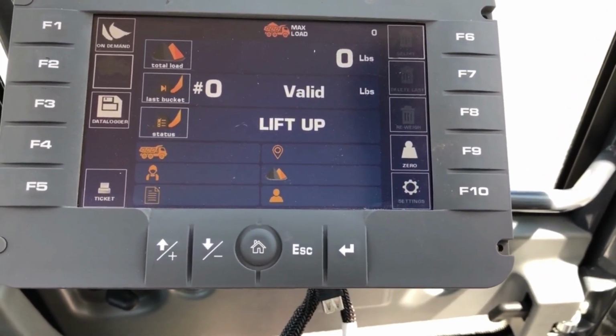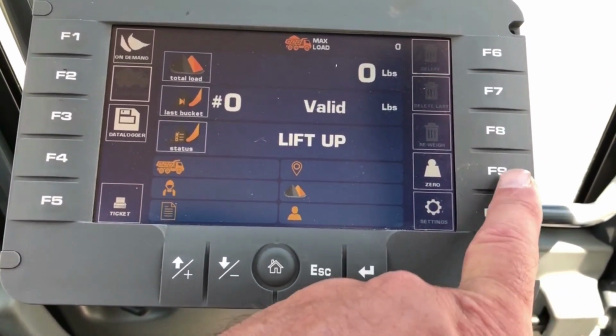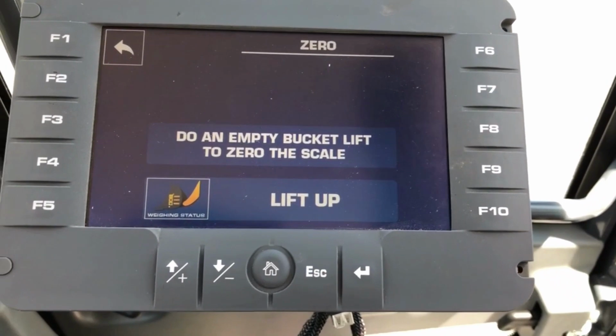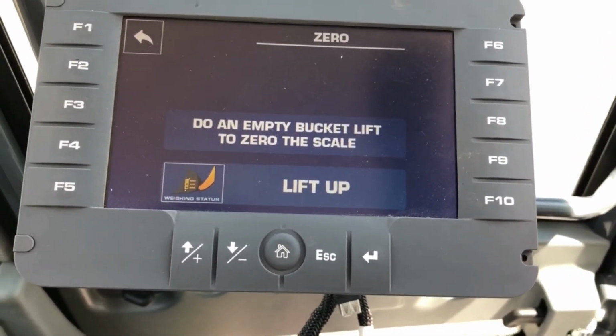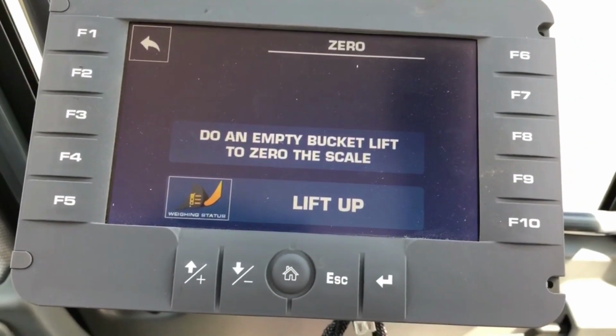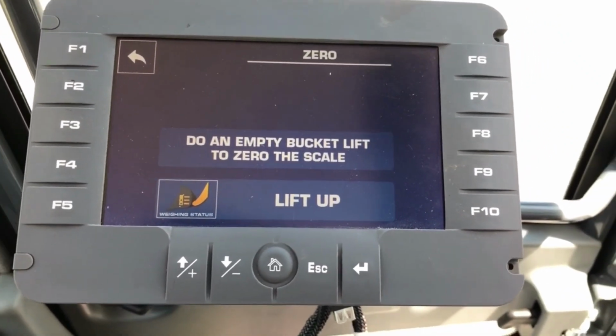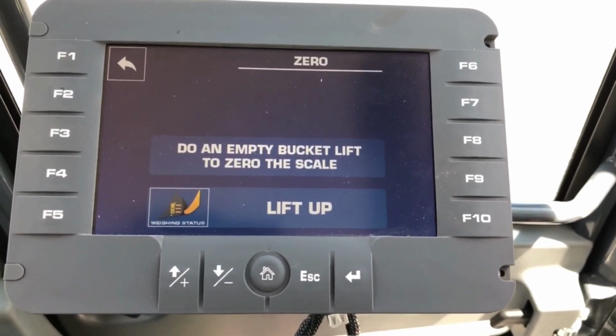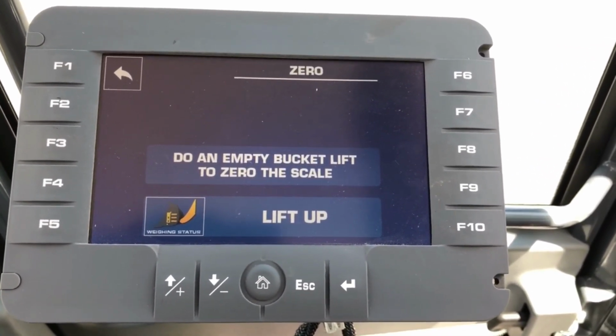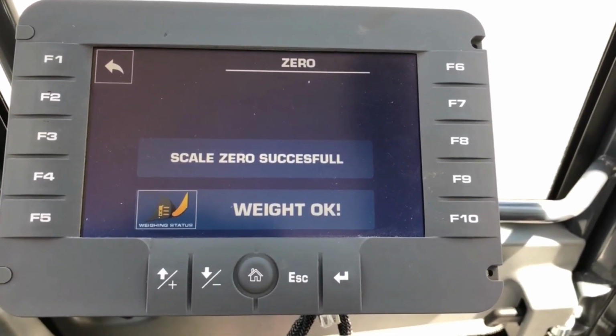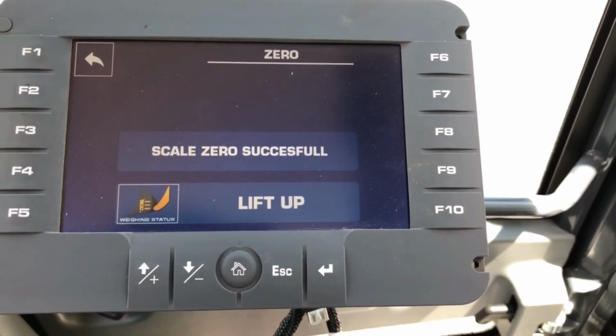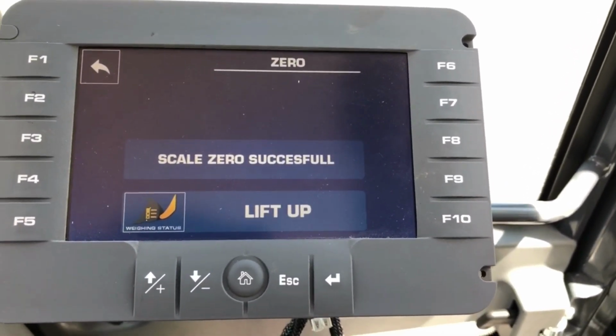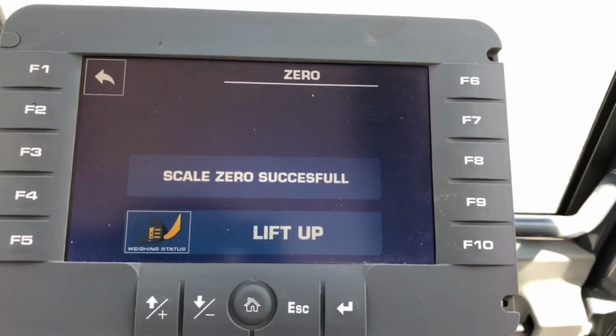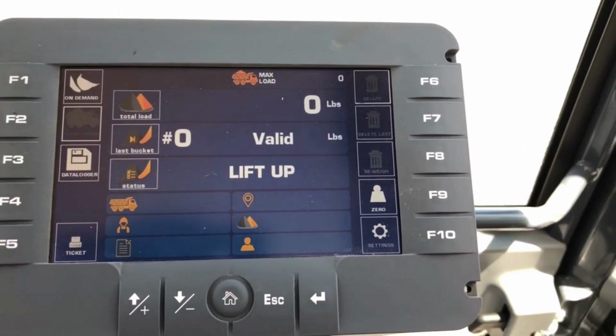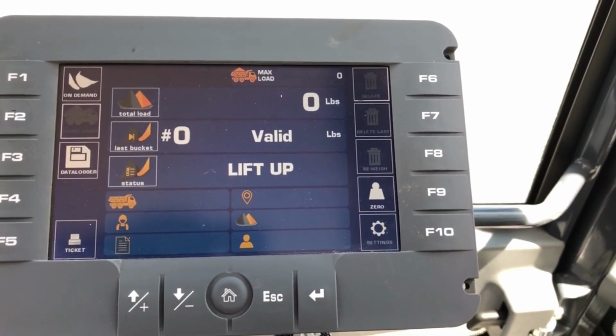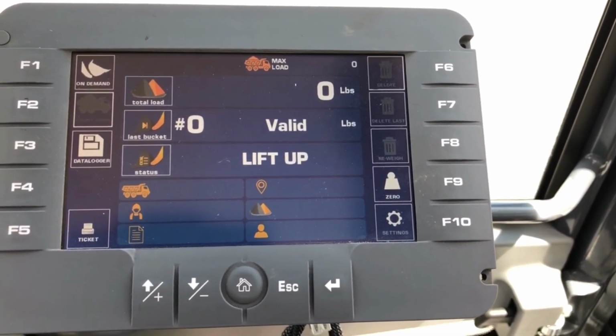The next thing we would recommend doing is zeroing the bucket. So we want you to hit F9. It's asking you to just please do an empty lift. So my bucket is empty still there, so I'm going to go ahead and do a lift. And it says that it was successful. Come back down, and then I'm going to hit F1. Now the scale is calibrated and zeroed and ready to weigh your material.